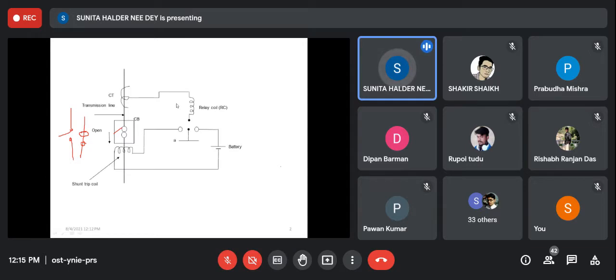So the relay coil actually energizes this contact. When the relay coil is energized, it will attract this contact like a solenoid. When it attracts this contact, as per the figure, this contact A will move upward and close the circuit. That means it is energizing some coil, called the shunt trip coil or trip coil. So in a relay, actually there are two coils. The relay coil is always energized using the system current by the CT, because a relay is a low power device. Every time it is energized, but it is energized with the system current.